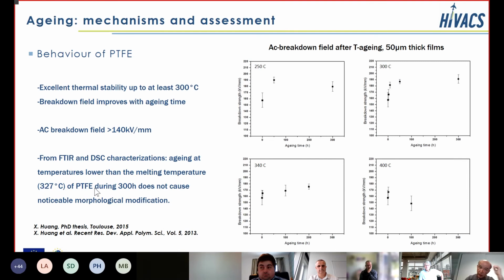If we look at similar things for PTFE, there is also work on the breakdown field achieved after thermal aging up to 200 or even 400 degrees C. Here, at 250, 300, 340 degrees C, the breakdown field as a function of aging time. We can see that for this material there could apparently even be an improvement of the breakdown field with aging, and there was also no evolution considering the infrared spectroscopy, for example. So it seems that the materials can really withstand the temperatures that we are working with, at least these two kinds of materials.